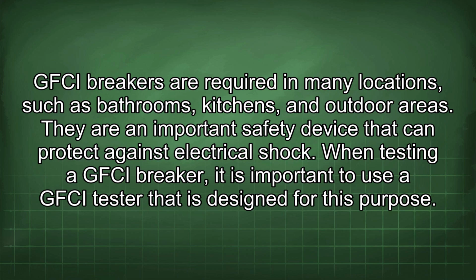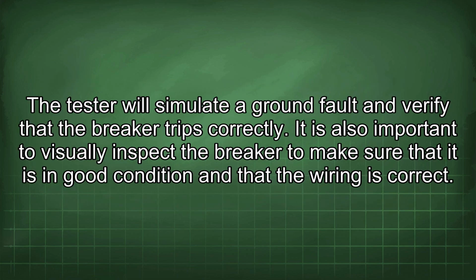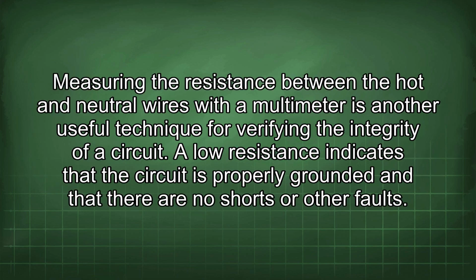When testing a GFCI breaker, it is important to use a GFCI tester that is designed for this purpose. The tester will simulate a ground fault and verify that the breaker trips correctly. It is also important to visually inspect the breaker to make sure that it is in good condition and that the wiring is correct. Measuring the resistance between the hot and neutral wires with a multimeter is another useful technique for verifying the integrity of a circuit.